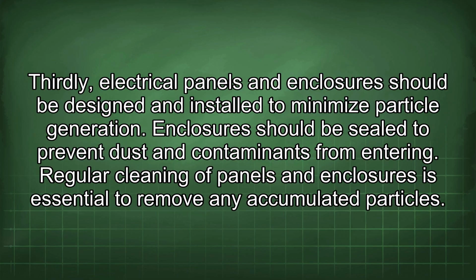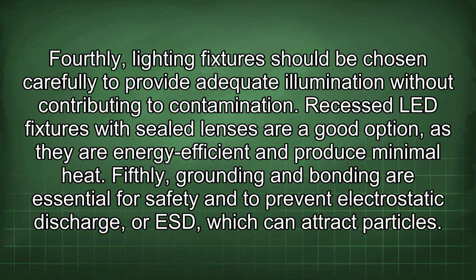Thirdly, electrical panels and enclosures should be designed and installed to minimize particle generation. Enclosures should be sealed to prevent dust and contaminants from entering. Regular cleaning of panels and enclosures is essential to remove any accumulated particles. Fourthly, lighting fixtures should be chosen carefully to provide adequate illumination without contributing to contamination. Recessed LED fixtures with sealed lenses are a good option, as they are energy efficient and produce minimal heat.